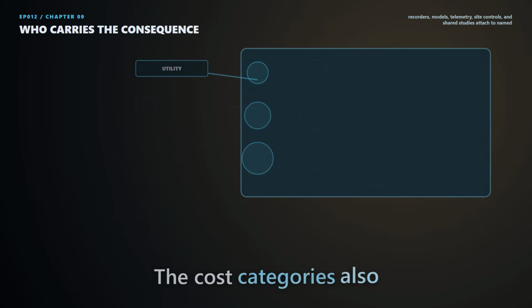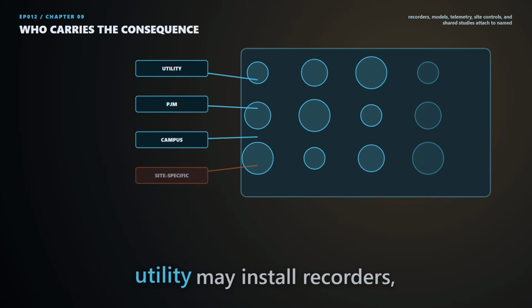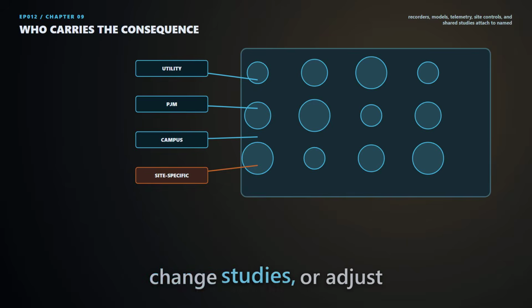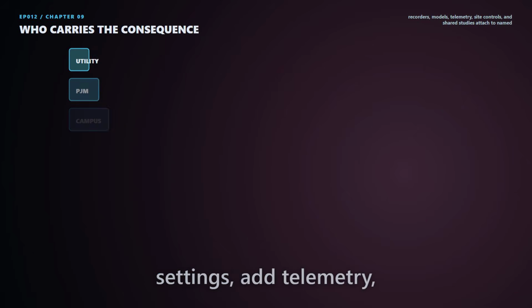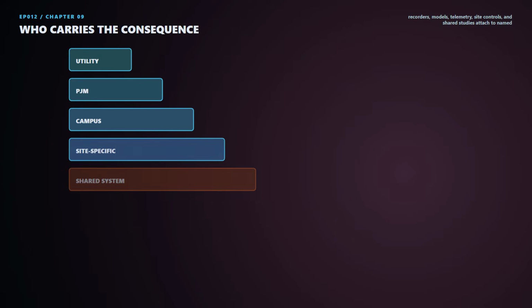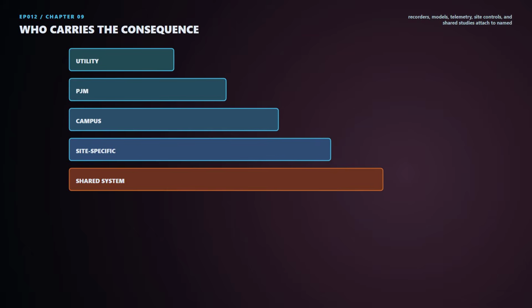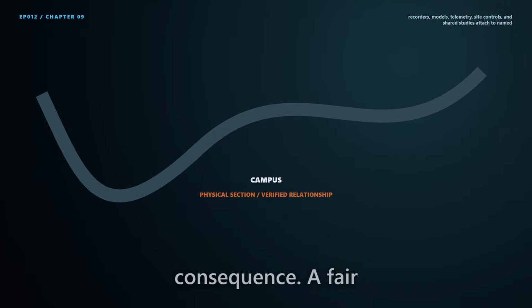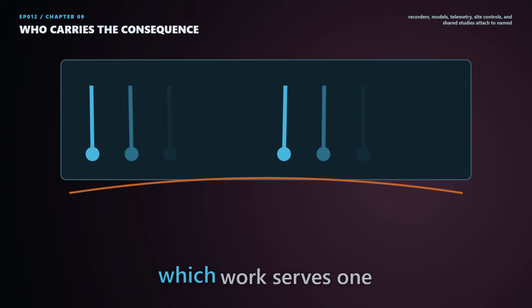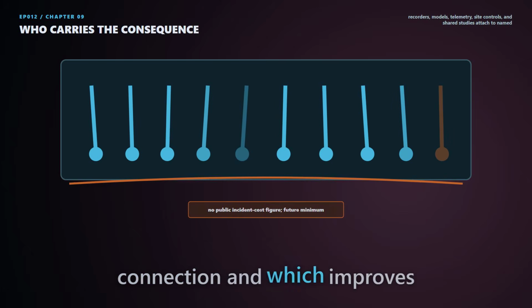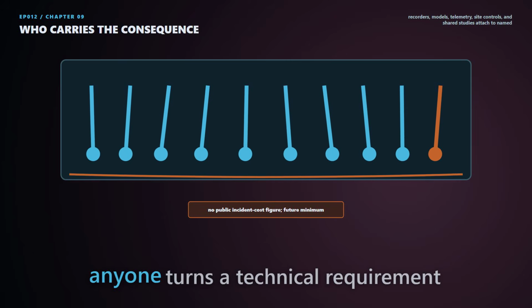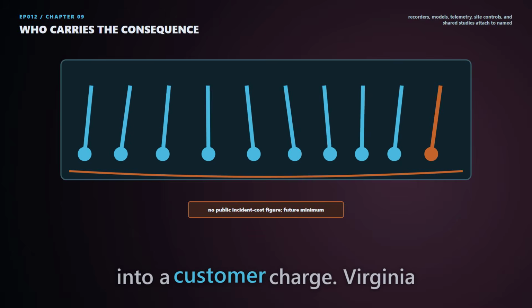The cost categories also occur at different boundaries. The utility may install recorders, change studies, or adjust transmission operations. A campus may revise controller settings, add telemetry, or replace protection equipment. PJM and neighboring utilities need models for the regional consequence. A fair allocation has to identify which work serves one connection and which improves a shared system before anyone turns a technical requirement into a customer charge.